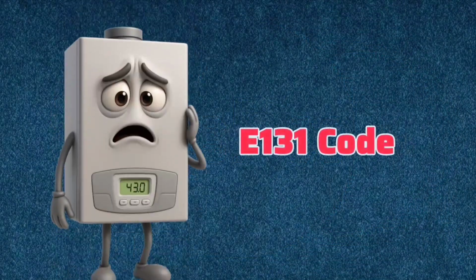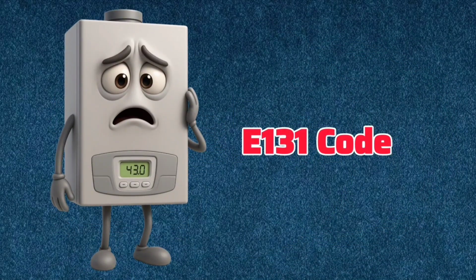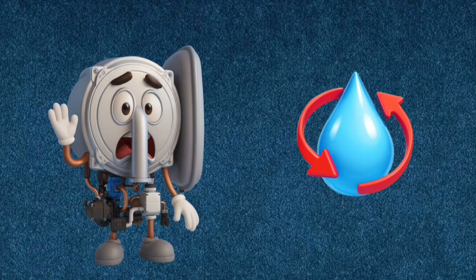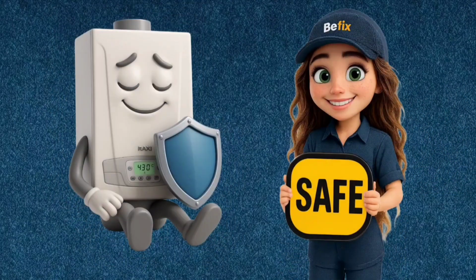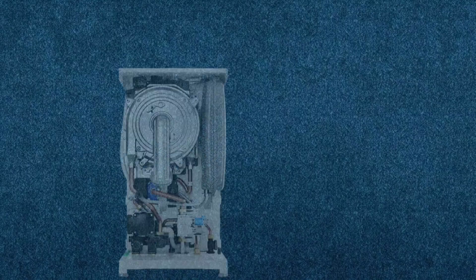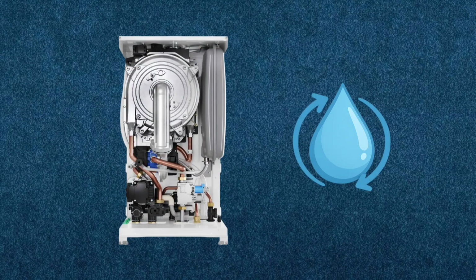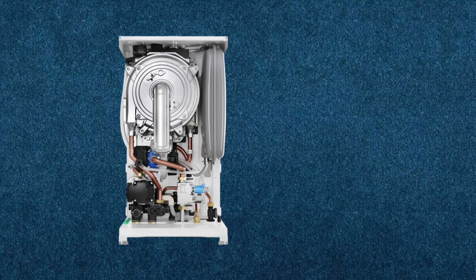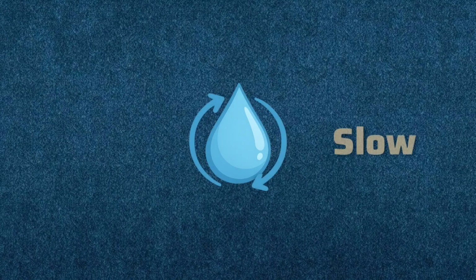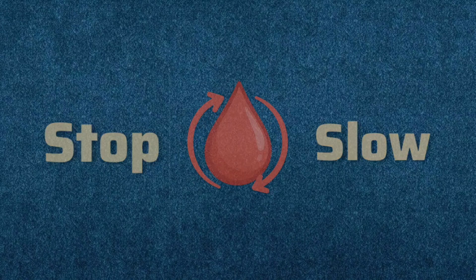Today we're looking at the E131 fault code on Baxi boilers, which means your boiler has overheated. This is a safety cutout designed to prevent damage. Your boiler works by circulating water through the system to carry heat away. If that circulation slows or stops, the boiler water overheats quickly.